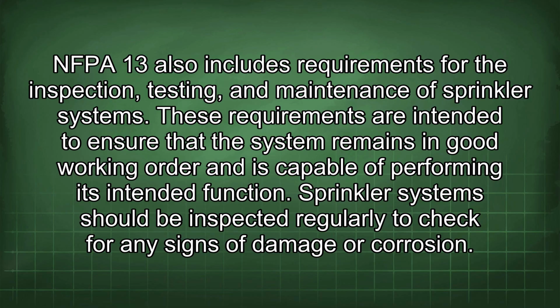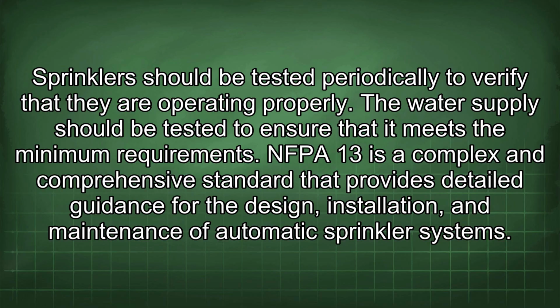NFPA 13 also includes requirements for the inspection, testing, and maintenance of sprinkler systems. These requirements are intended to ensure that the system remains in good working order and is capable of performing its intended function. Sprinkler systems should be inspected regularly to check for any signs of damage or corrosion. Sprinklers should be tested periodically to verify that they are operating properly. The water supply should be tested to ensure that it meets the minimum requirement.